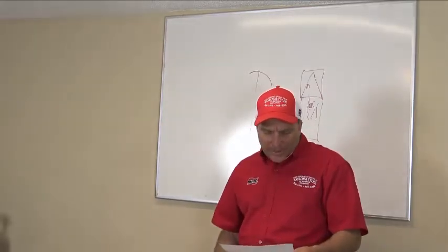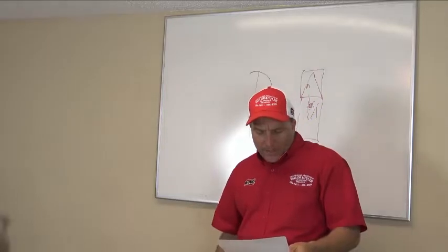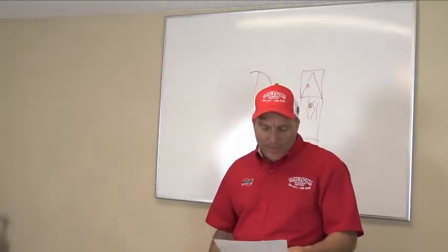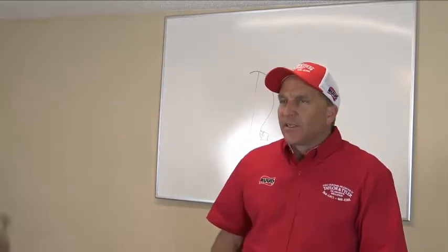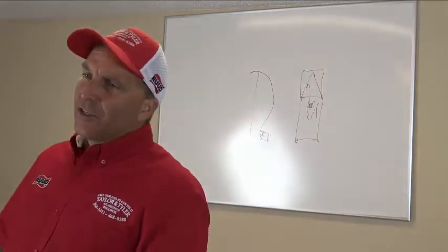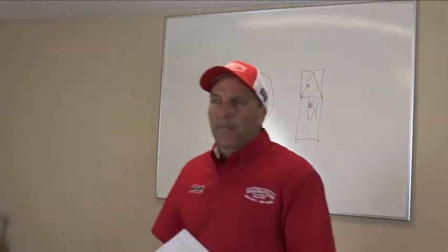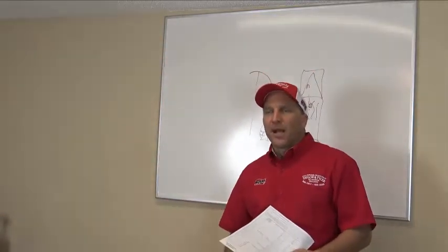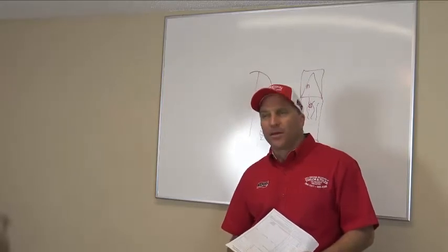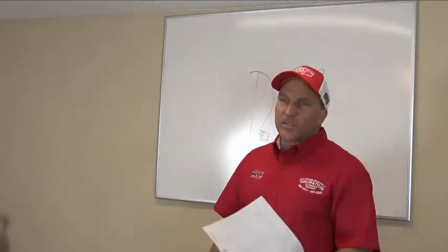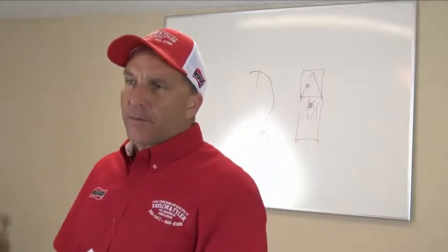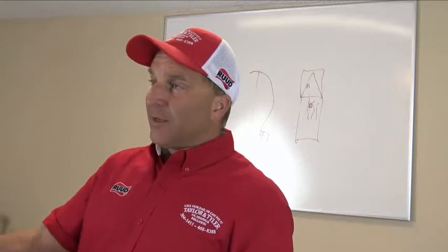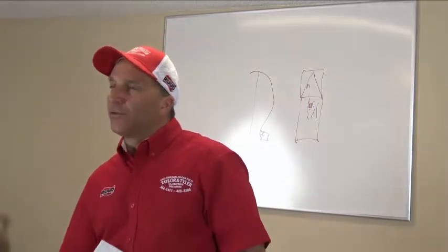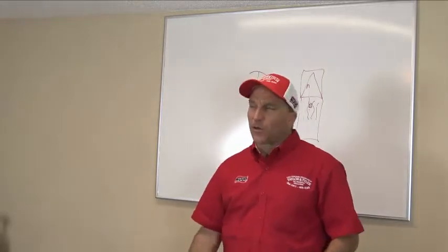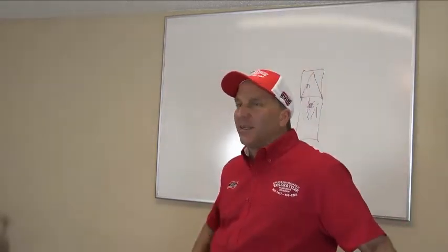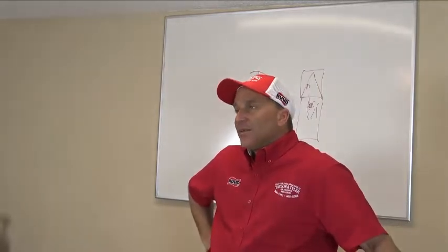All right, refrigerant leaks. None visible or undetectable. Well, how do you know if you got refrigerant leaks in your system, guys? Well, if you go out there and you put your gauges on your system and your system's low on refrigerant, guess what? Not necessarily. Because how do you know if it was charged up properly to begin with? What if your subcooling is 4? After you cleaned it and everything's working fine and your subcooling's 4. He's never had a problem with the cooling, but your subcooling is 4. Does that mean he has a leak in the system? Not necessarily. No, it really doesn't.